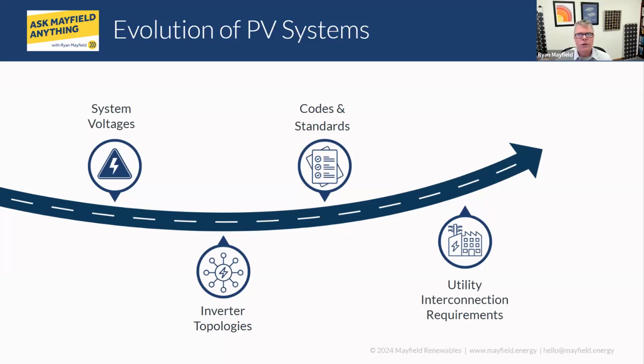The current code very often says we can use USE-2 conductors for our free air conductors, which is what we were using way back when we were doing grounded, isolated inverters. So that's definitely something that comes up - being able to reuse that equipment. But you also need to check: is it in good working condition before you start reusing it?